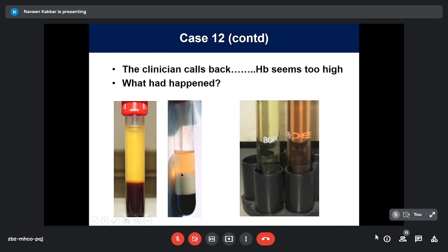Now, when you estimate your hemoglobin here, the white cells cause turbidity. Hemoglobin in the instrument is read spectrophotometrically after lysis of the red cells. So if you have white cells in that solution, they'll cause turbidity. And because the reading is spectrophotometry, turbidity causes a high reading. So you'll get a spuriously high hemoglobin if the patient has a very high TLC.